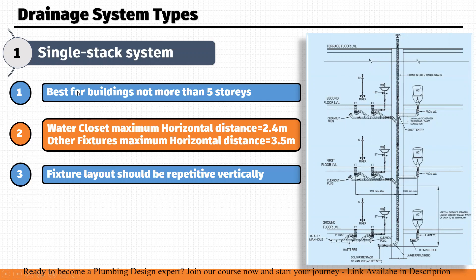There are some points we have to consider while designing this kind of system. The first point is that the single stack system is suitable for buildings less than five stories — it is not meant for high-rise buildings, only those with fewer than five floors.